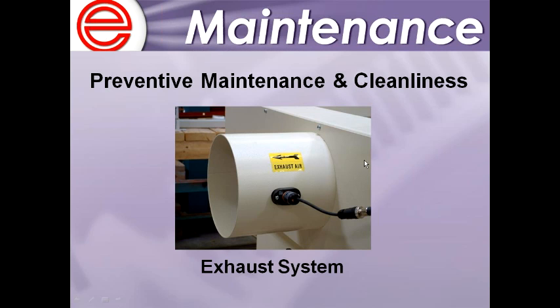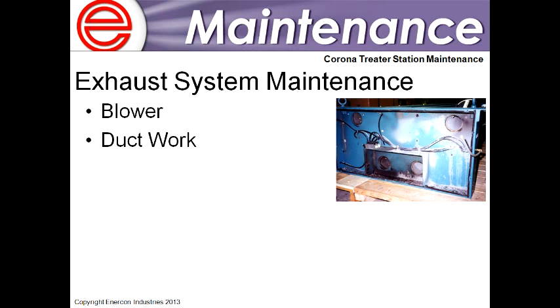All right, and then the exhaust system, we'll just go over some basic things of the exhaust system. That's something that a lot of people take for granted. Again, it's removing that heat and ozone, so it is very important, but it's usually something that's installed once and left alone. But it is a good idea to periodically check the blower. Just make sure that the blower is rotating the correct direction in case electrical work takes place or whatever over the years. Also the duct work, inspect that.